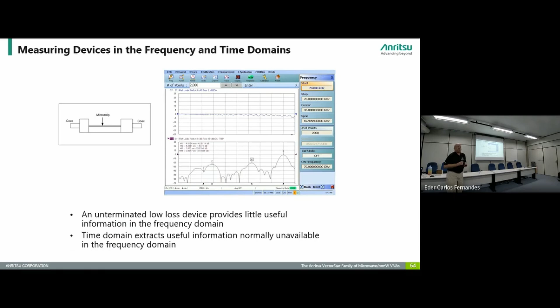Well, time domain allows us to resolve things, and depending on how much frequency range you have in your VNA, the resolution improves. So if you get up to these higher frequency, higher bandwidth VNAs, you can see we get down to millimeters of resolution. So we can accurately pinpoint where these problems reside. The resolution is inversely related to the bandwidth of the VNA, so the more bandwidth, the better the resolution. So the TDR display is a step response on a low pass time domain, and what we're able to profile is the actual impedance of the line as a function of distance or time.